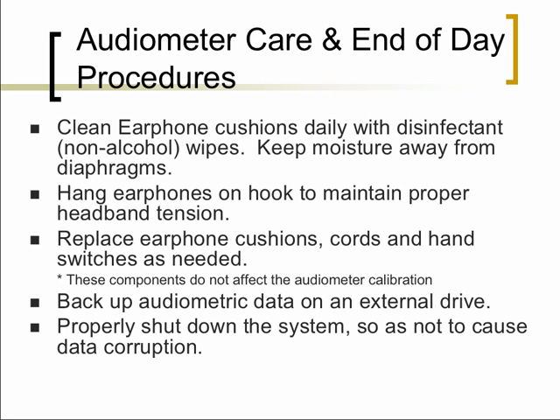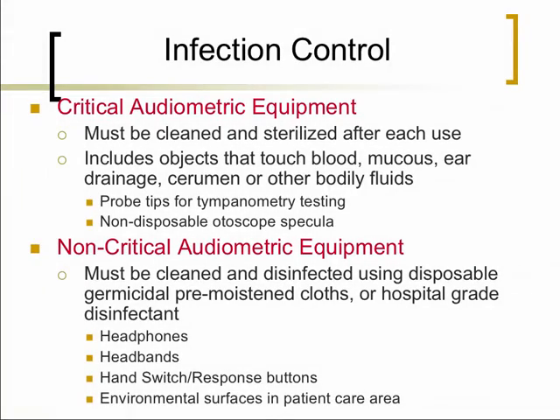And if there's any data on the audiometer, especially with those digital audiometers, you want to make sure that you back them up. And you want to properly shut down the system rather than just pulling out the plug. You want to make sure that you use the power button on the audiometer before you turn off the power for the whole room or such. Some more things for your reference about critical audiometric equipment and non-critical audiometric equipment maintenance. So all this is that biological calibration.